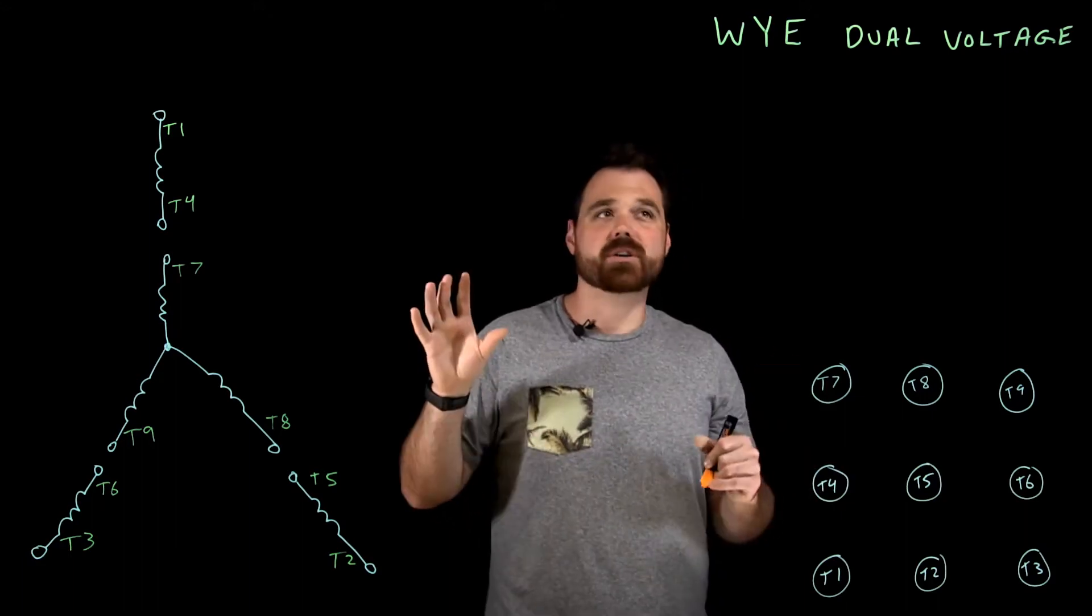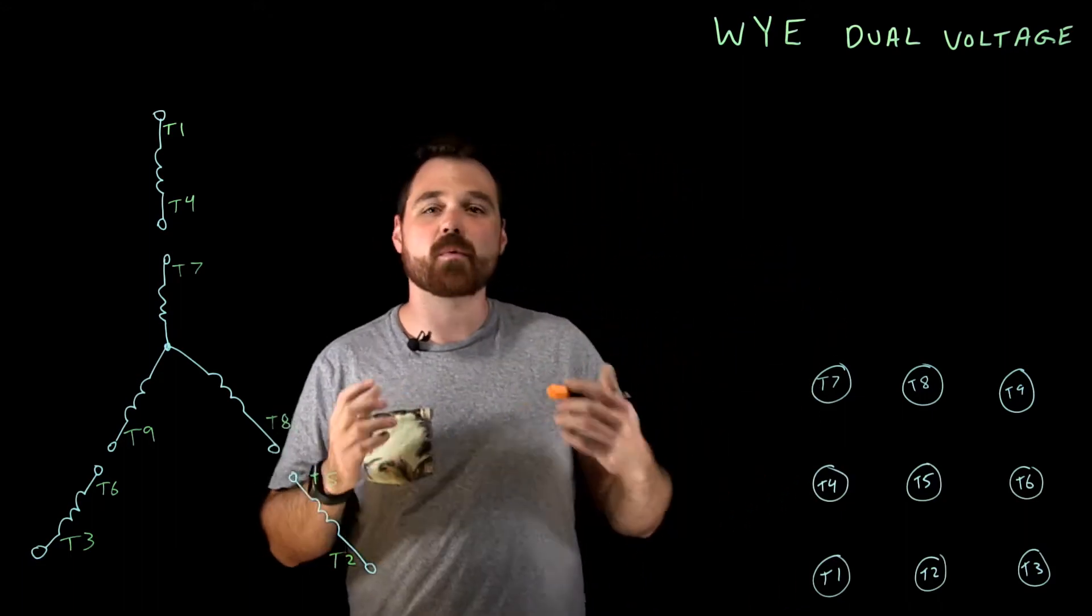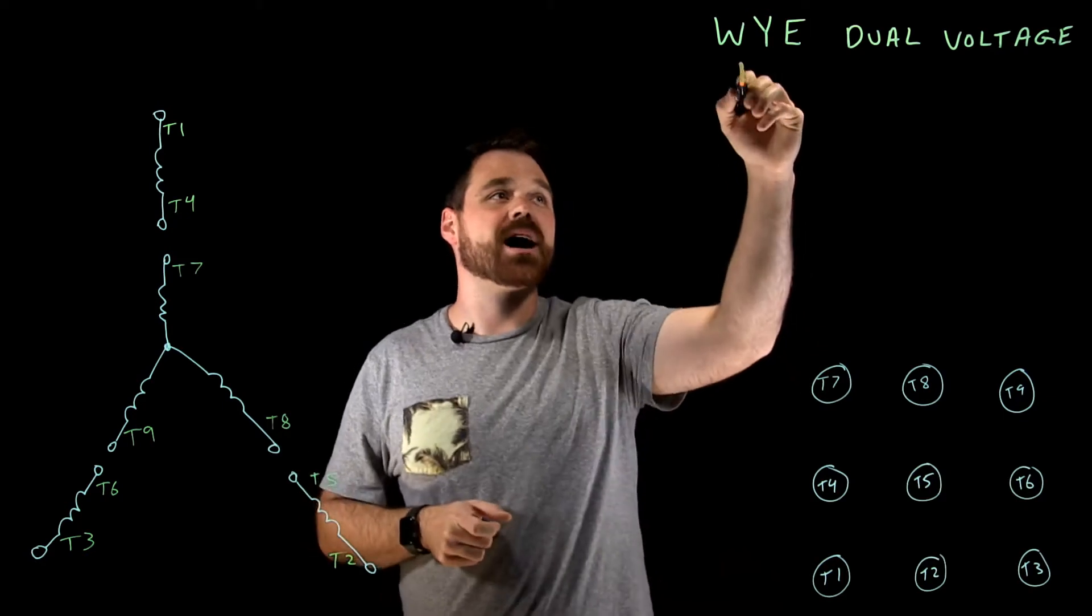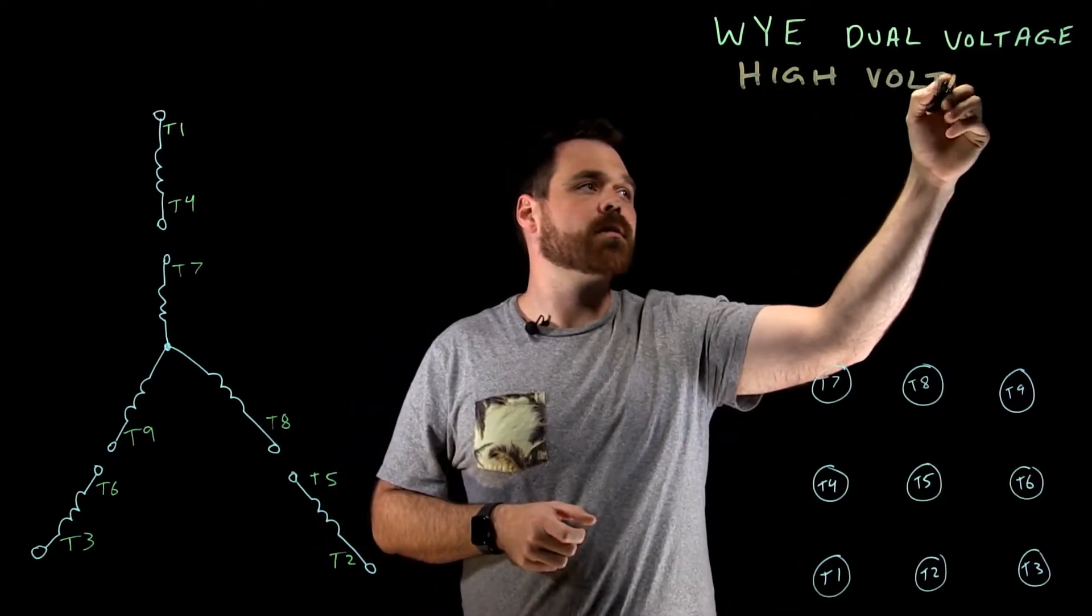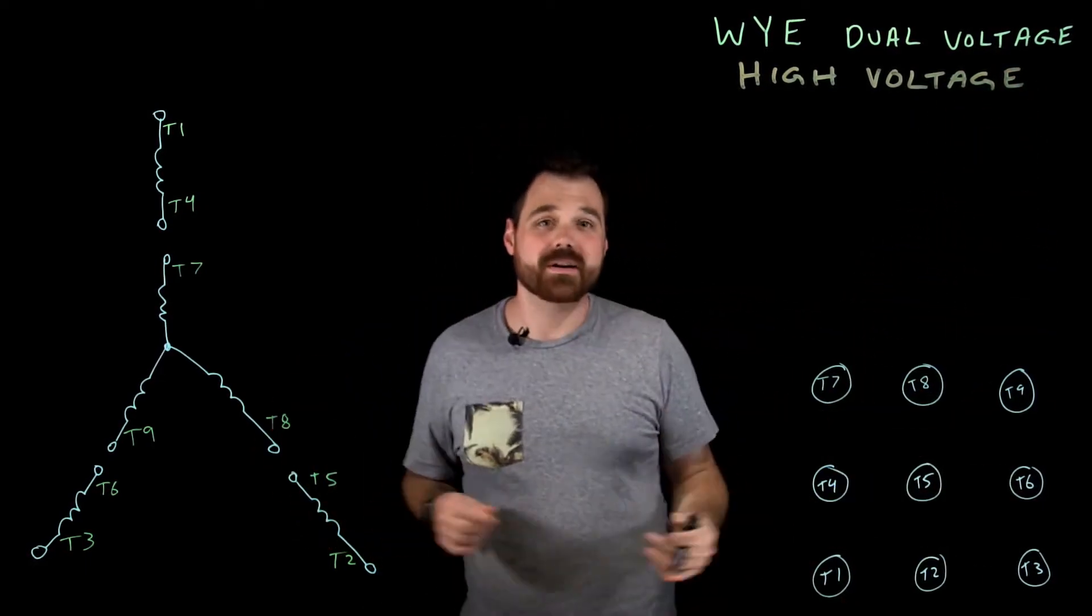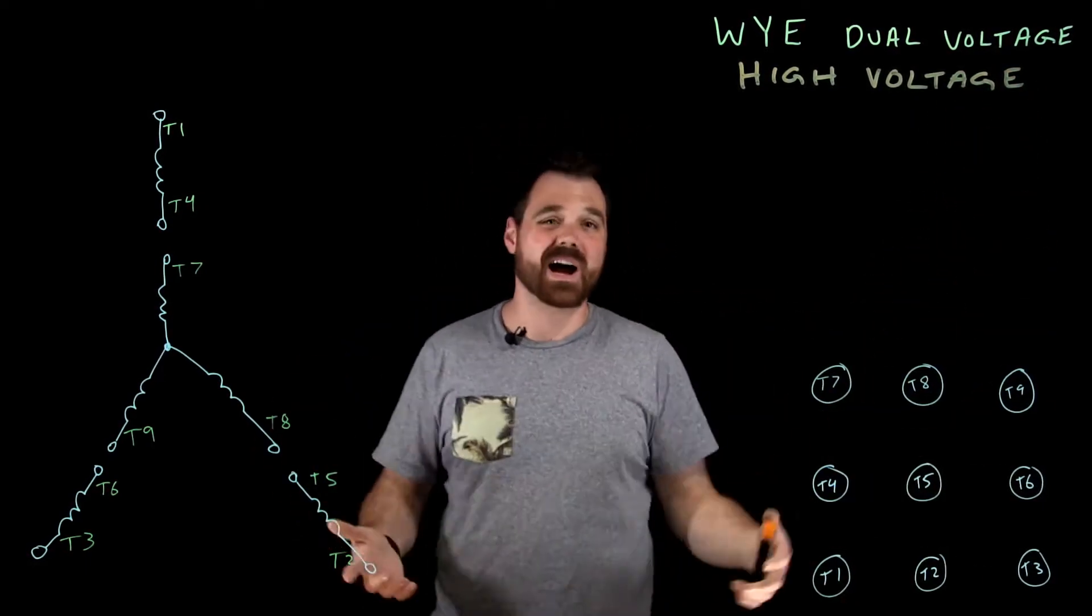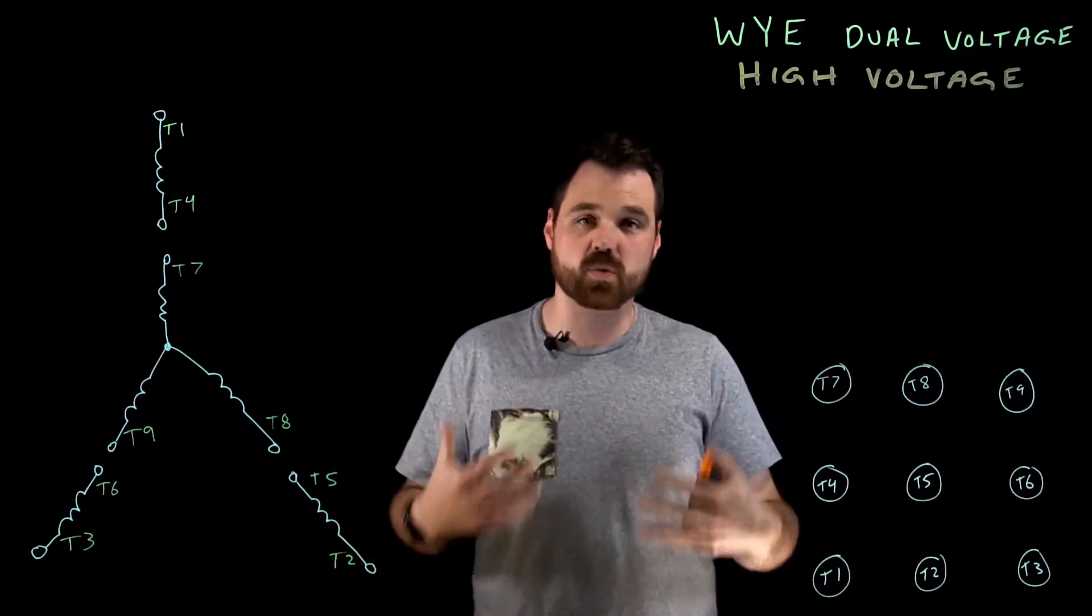In this case, we're going to talk about a Y dual voltage nine lead motor, and we're going to talk about terminating it in its high voltage connection. So the idea behind this Y motor is I can connect it to a low voltage or a high voltage depending on how I connect those windings.